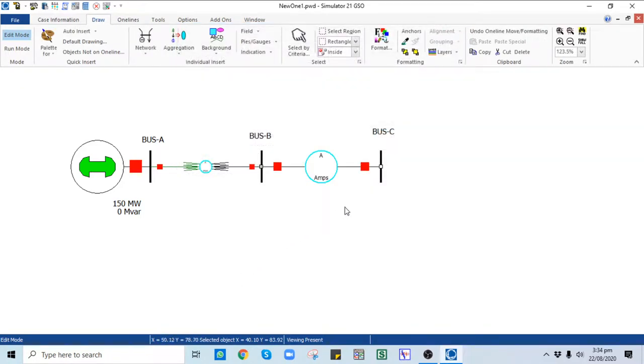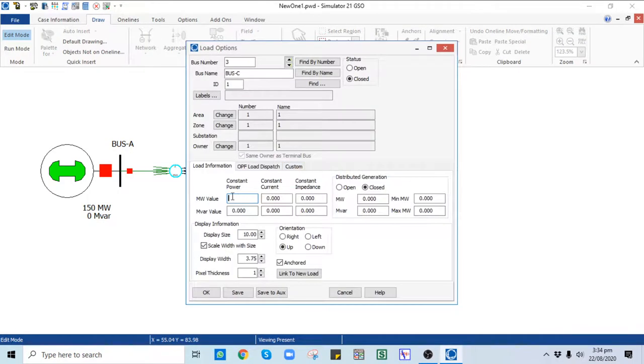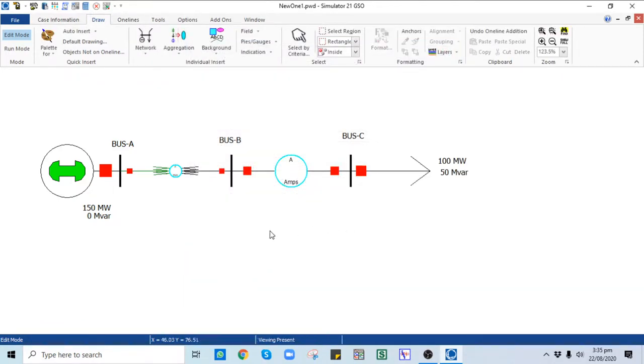The last component is the load on Bus C. The generator has a megawatt capacity of 150 MW; we can set the load to 100 MW, with a MVAR value of 50 MVAR at 0.95 power factor. This is constant power load modeling. If you want to model load as constant current or constant impedance, those options are available but are mostly used in dynamic stability analysis. In Display options, select orientation to Right, check the Anchor button, and click OK.